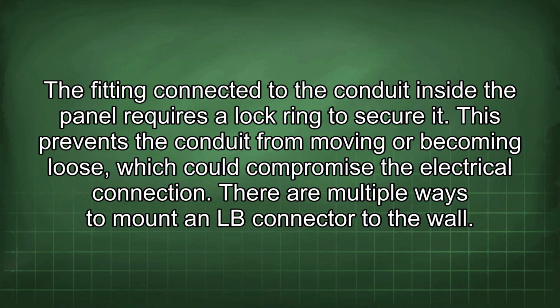Fitting connected to the conduit inside the panel requires a lock ring to secure it. This prevents the conduit from moving or becoming loose, which could compromise the electrical connection. There are multiple ways to mount an LB connector to the wall.